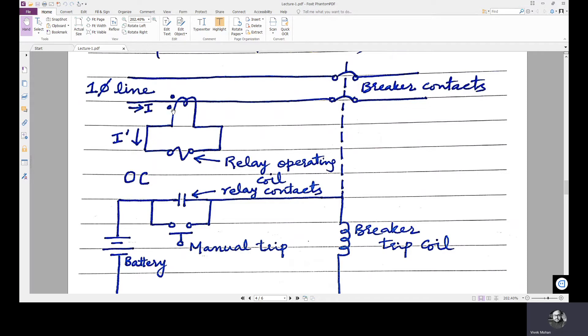The CT converts primary current in the kilo amps range to secondary currents in the 0 to 5 amps range. I dash is in the 0 to 5 amps range for convenience of measurement. The first advantage is safety — this secondary circuit is electrically isolated from the power circuit, so personnel working with relays will be safer. The second aspect is economy: as the relays operate at a lower level input, the relay's physical design can be smaller and less expensive. So the use of instrument transformers makes the protection system more economic.